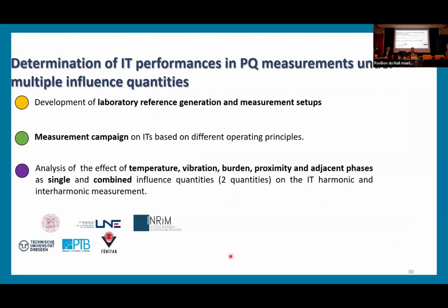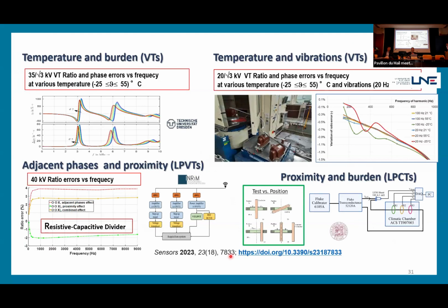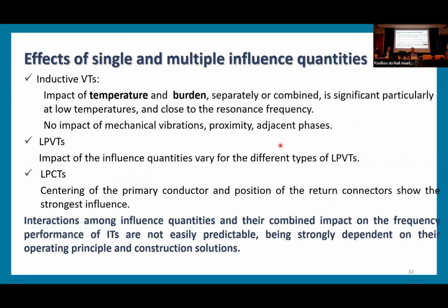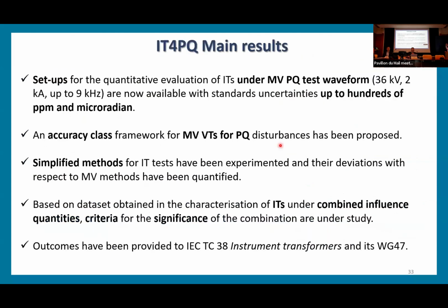Another interesting thing was the testing of several types of instrument transformers against influence factors like temperature, adjacent phases, the proximity, the position of the cables inside a Rogowski coil, and the vibration. Summarizing, the main results of IT4PQ were the development of reference setups for voltage transformer and current transformer calibration up to 36 kilovolts, 2 kiloamps, 9 kilohertz, the definition of a new PQ accuracy class, the verification of the influence factors on the performance of instrument transformers when measuring harmonics.